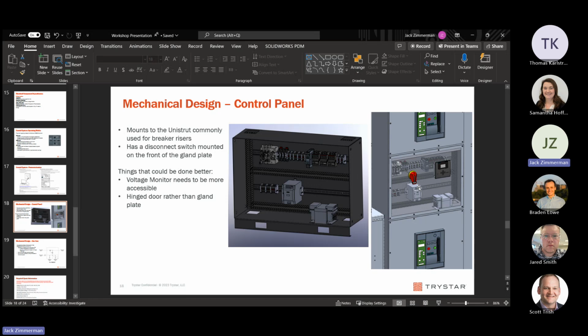Like UV print for it and stuff. Yeah, so this has some special UV prints on it. There's one that sits underneath this little handle here, which says voltage will still be present under generator power. And what that means is, if you flip that switch and go into that panel, if you have your generator on, that panel is still energized with 480 volts. And also the utility top side of that switch is always energized with 480 unless you disconnect at the transformer. It makes sense because this docking station is the first disconnecting means in the entire system.